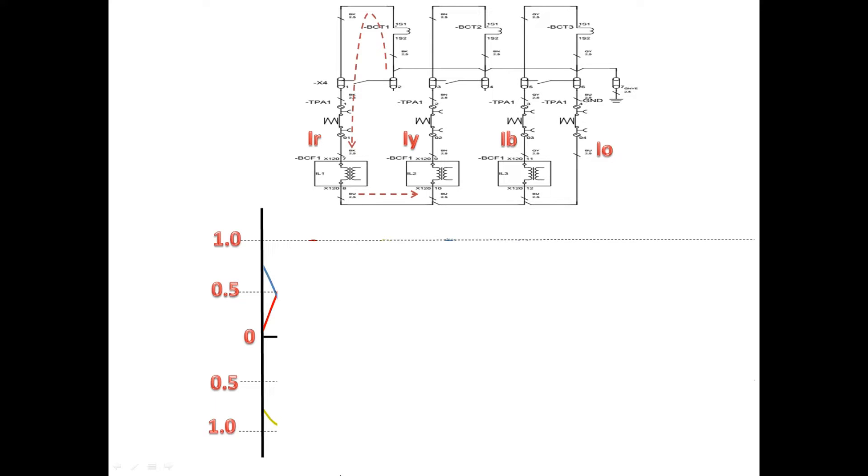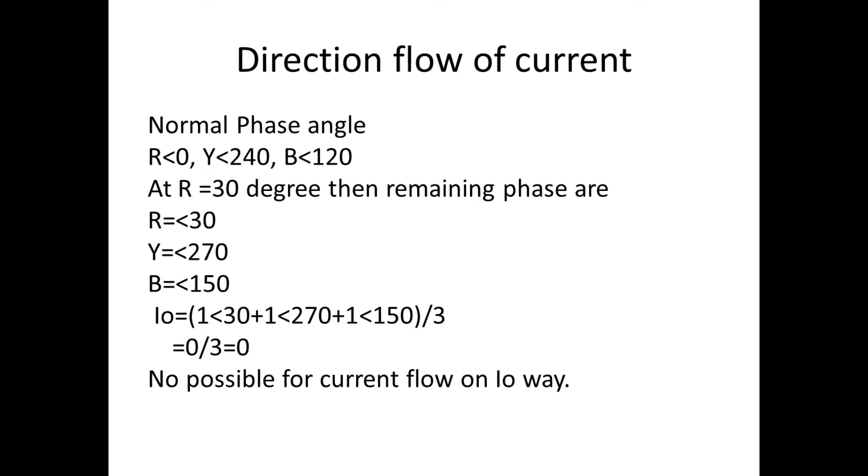Now we check the neutral path, is it possible to flow in neutral path or not? Normal phase angle difference is 0, 240, 120. Now we are seeing at 30 degrees, so all phases will have 30 degree phase shift. When you go for finding the zero sequence current, it is zero, so no possibility to flow in I0.